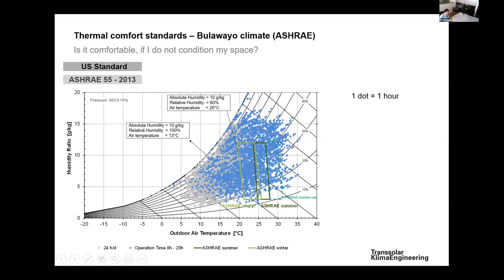A few words on relative versus absolute humidity. Absolute humidity is measured in grams per kilogram. Relative humidity depends on temperature. For example, with 10 grams of water per kilogram of air at 13°C, the air is fully saturated — relative humidity is 100%. But the same absolute humidity of 10 grams per kilogram at 20°C gives only about 60% relative humidity, because warmer air can hold more water before becoming saturated.